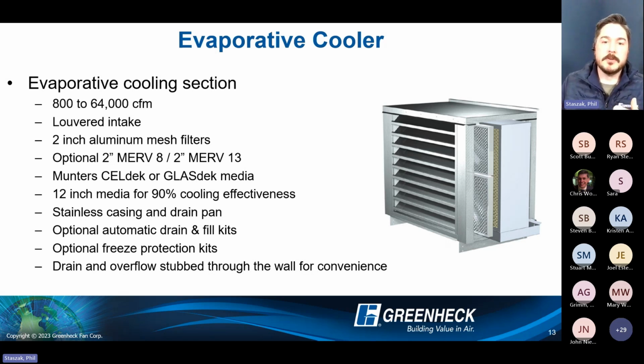So water is being introduced into the airstream. So it's very important to do an automatic drain and flush sequence of that pan to introduce fresh water supply to extend the longevity of that media. So it is something that we offer. It's an auto drain and flush kit from the factory, once a day for 5 minutes. It'll introduce fresh water supply and flush that pan out. So just a fun little fact there.